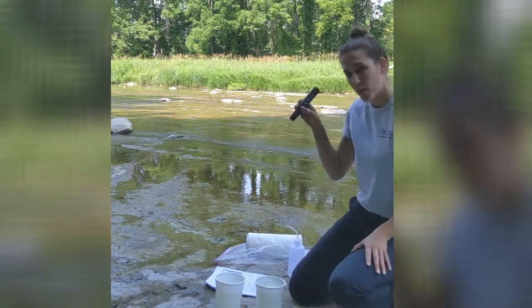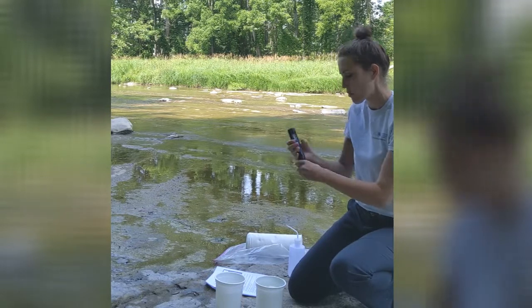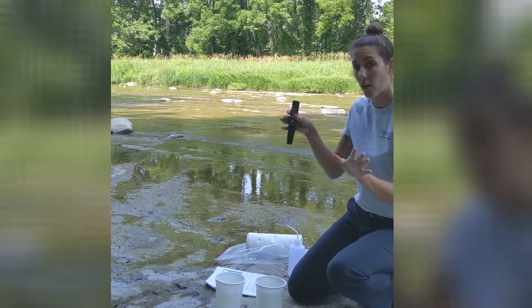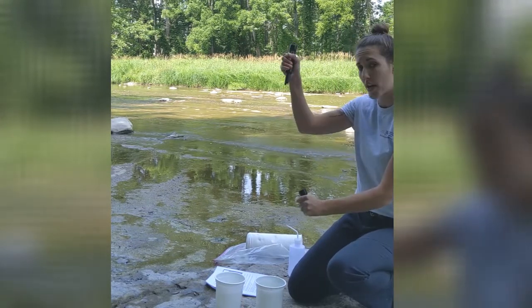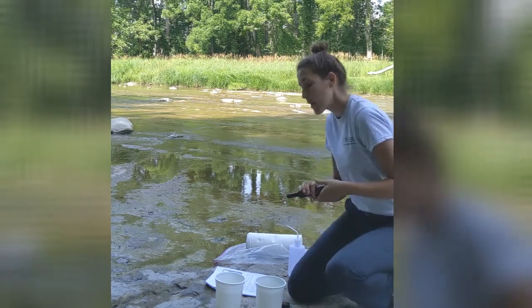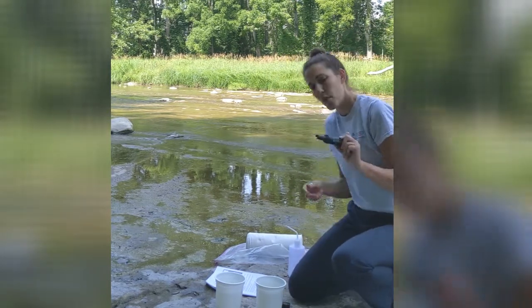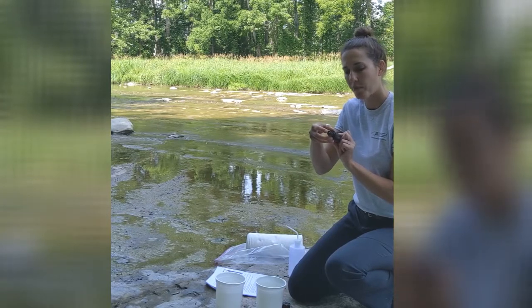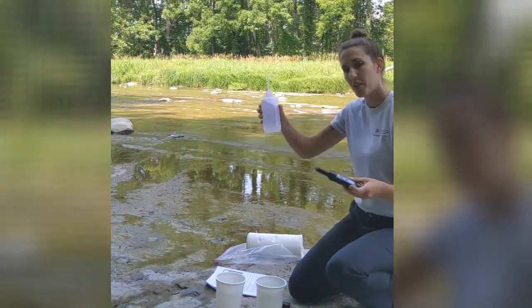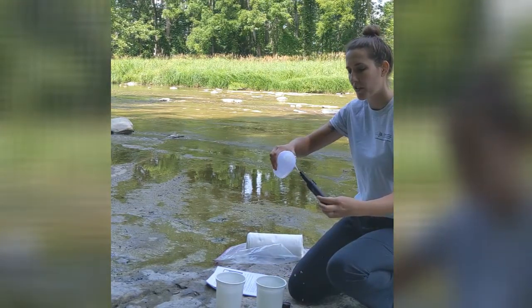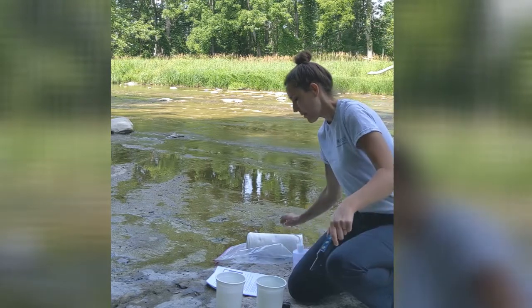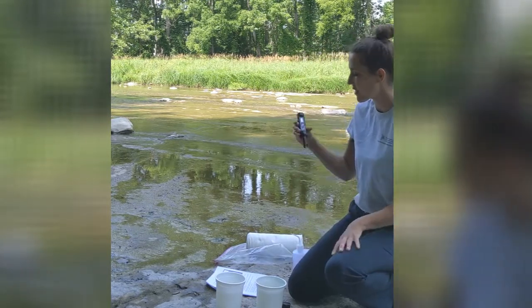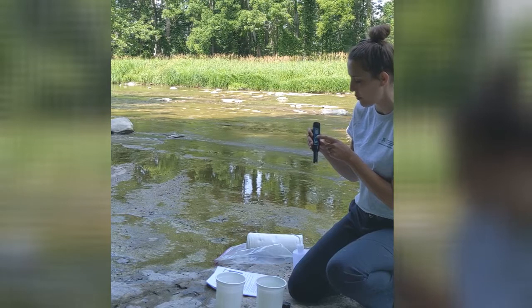Then we're going to find our conductivity probe and remove the cap. You don't need to twist at all for the cap, all you have to do is pull straight down. Then you're going to rinse that probe, which is down inside the bottom, surrounded by plastic. Rinse it with distilled water, that rinse bottle at your site, and then press the on button at the top of your probe.